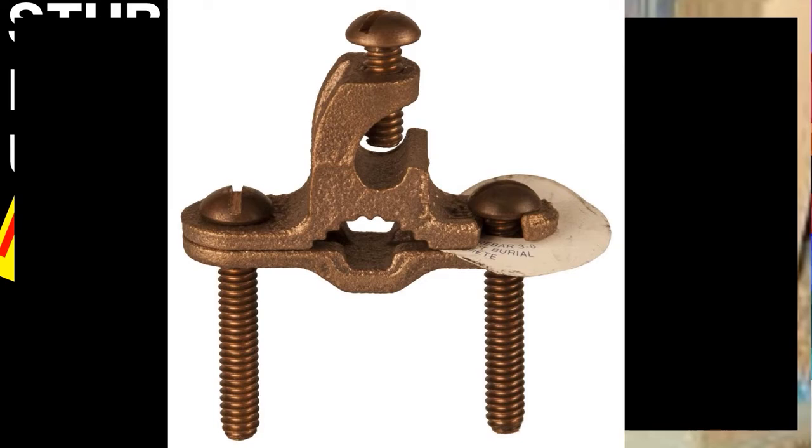So traditionally on a footing, the concrete people will come in and they will tie off their steel. We will come in with a fitting like this, and it's rated for rebar. It is also rated for direct burial and for concrete. And then we'll attach our number four to that, like so, and we'll have to leave a curl of wire laying out on the job site.